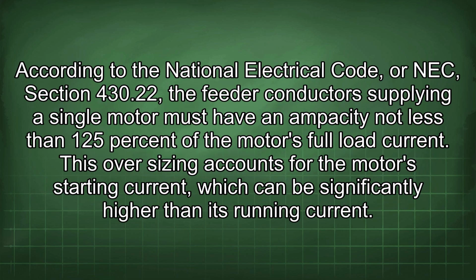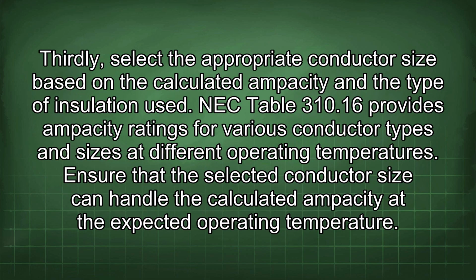According to the National Electrical Code, or NEC, section 430.22, the feeder conductor supplying a single motor must have an ampacity not less than 125% of the motor's full load current. This oversizing accounts for the motor's starting current, which can be significantly higher than its running current. Thirdly, select the appropriate conductor size based on the calculated ampacity and the type of insulation used. NEC Table 310.16 provides ampacity ratings for various conductor types and sizes at different operating temperatures. Ensure that the selected conductor size can handle the calculated ampacity at the expected operating temperature.